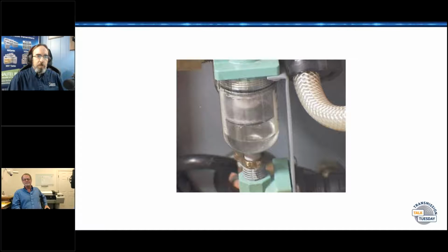We knew it had a pinprick air leak in it. But what was happening is this is one of those systems that has a small regulator that allows air to flow backwards, spraying the water into a little gold pan on top of the compressor head so the heat from the compressor makes it evaporate. That regulator had been tightened down too tight, so there was no backflow, and that moisture couldn't get out. So it just kept building up.